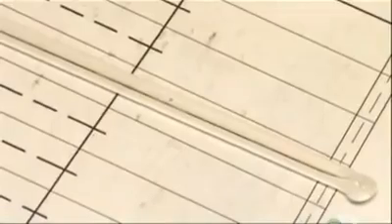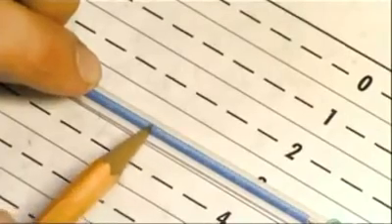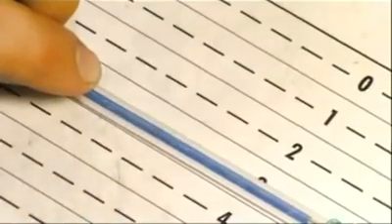They align the two scratches in the thermometer with markings on a printed grid. The distance between the two scratches often varies, so by measuring against this grid, they can calibrate the thermometer.